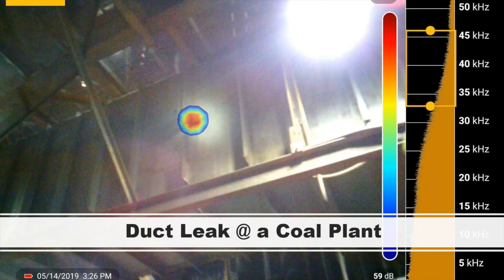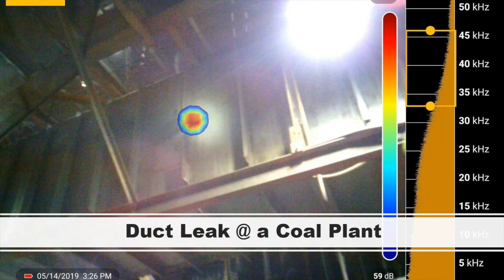Here's another cool one — and this is the last example. This is a huge duct at a coal plant that's sucking air out of the facility for safety reasons and their production process. This is an example of a vacuum leak — sucking air through this duct — with pretty serious safety implications for this particular plant. A neat and unconventional example of customers figuring out different and unique ways to use this tool to solve problems. The idea is that it's not about gas or air — it's about sound. When can sound help you identify or pinpoint a problem?